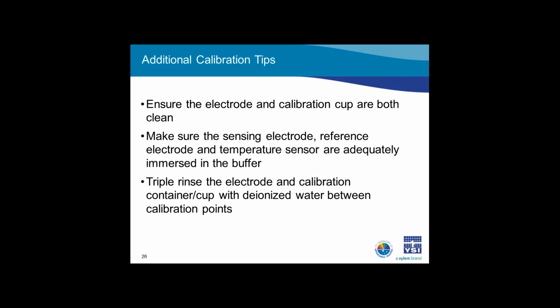There are several other things to consider when performing a calibration to ensure accurate measurements. You will want to make sure everything is clean so we don't contaminate buffer solutions. This includes the electrodes, temperature sensor, and calibration container. All should be cleaned and dry before starting.